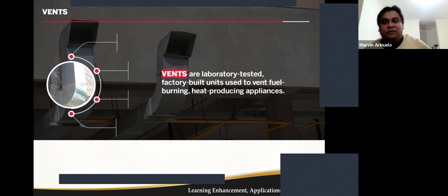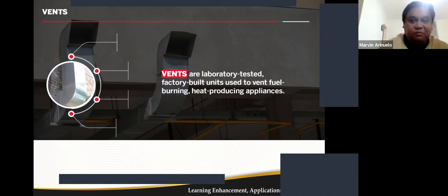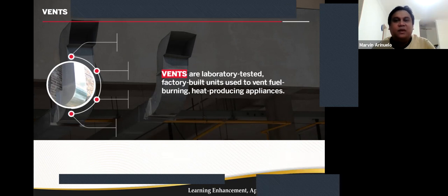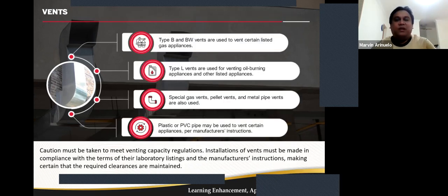Vents are laboratory-tested, factory-built, used to vent fuel-burning, heat-producing appliances. Specific types of vents have specific uses. For example, Type B and Type BW vents are used to vent certain listed gas appliances. So let us go to another slide. Type L vents are used for venting oil-burning appliances and other listed appliances. Special gas vents, pellet vents, and metal pipe vents are also used. And plastic or PVC pipe may also be used to vent certain appliances per manufacturer instruction.